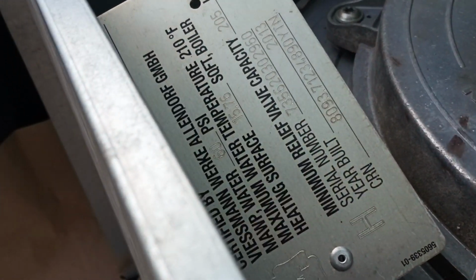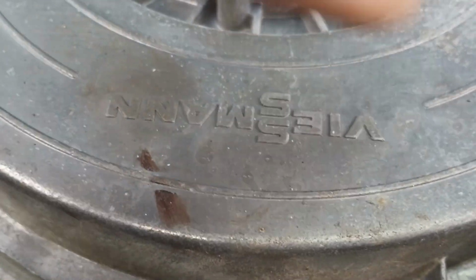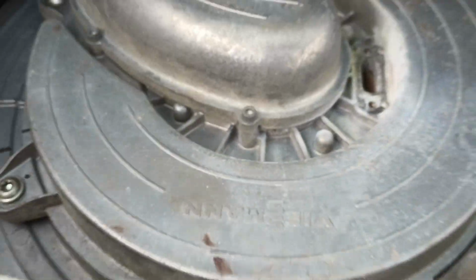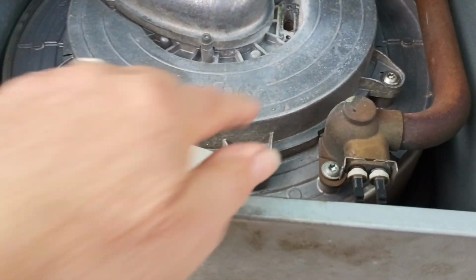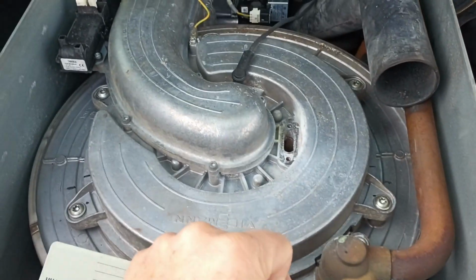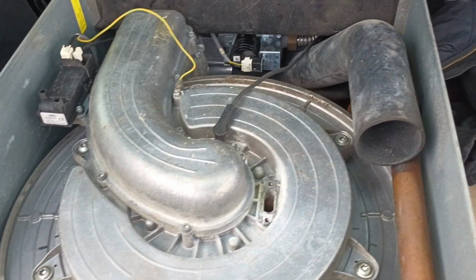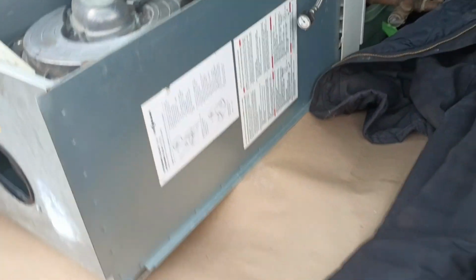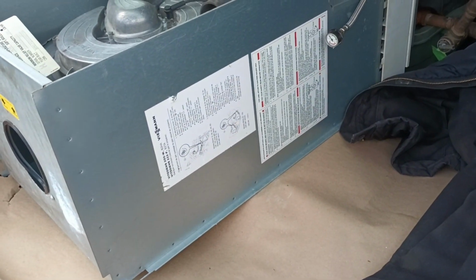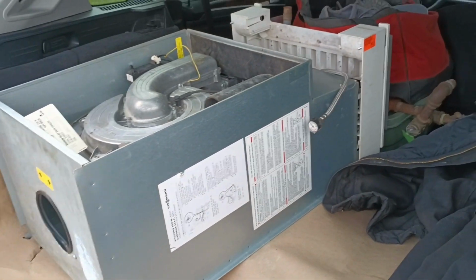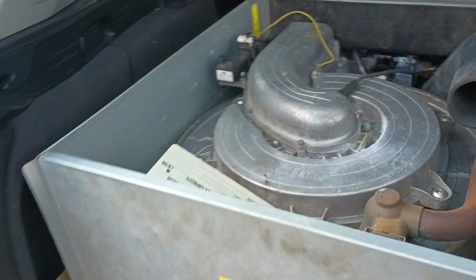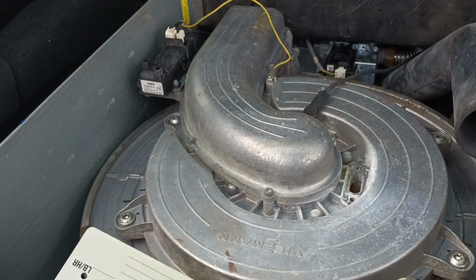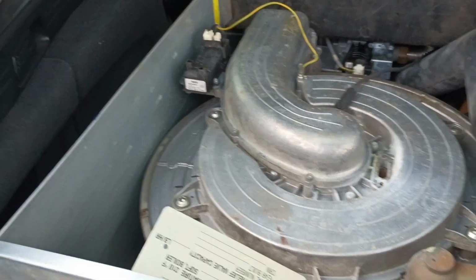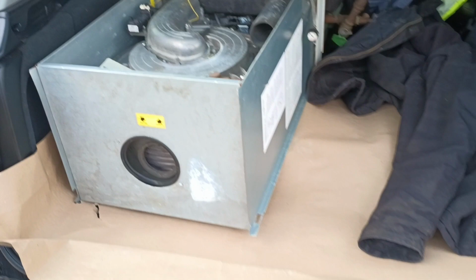So this is the carcass of a Viessmann. Got the name upside down. Viessmann. Anyway, gonna open it up, cut up the heat exchanger, and get an idea of why this unit was not heating the water like it should have. Actually, this stuff had glycol in it, so we'll do a little testing on it and chop it open and document some of that. So stay tuned.